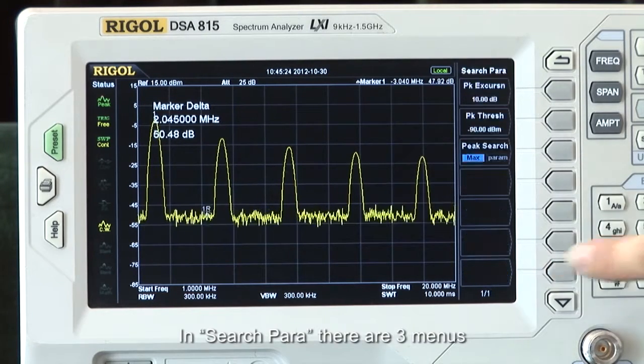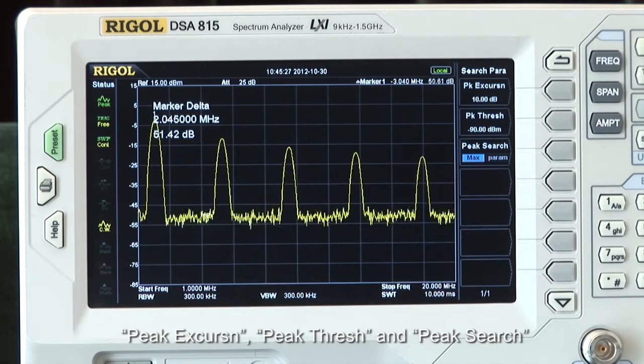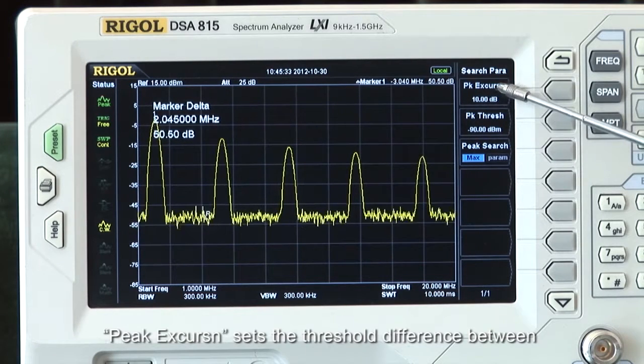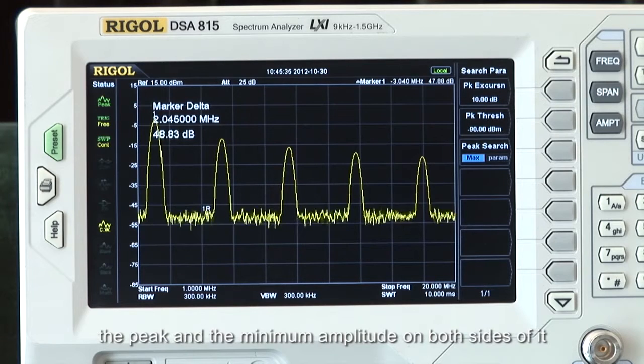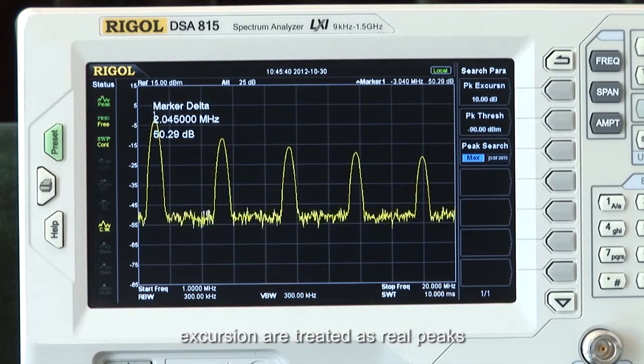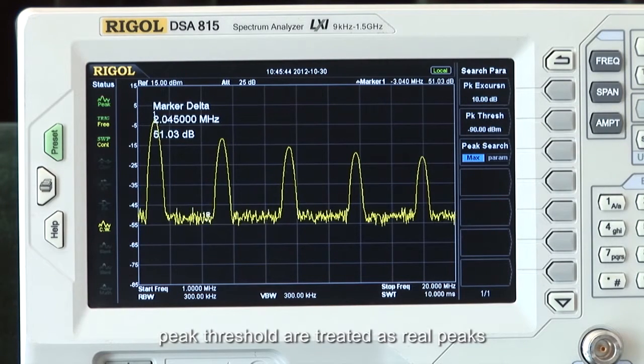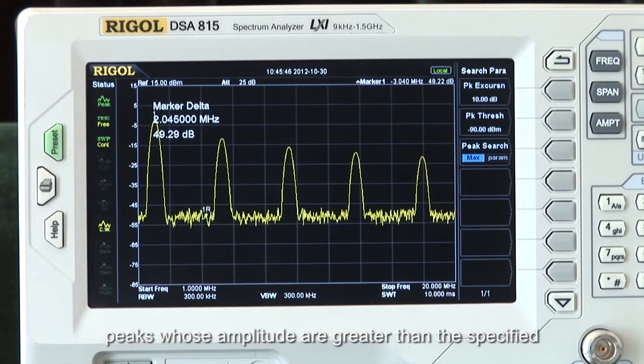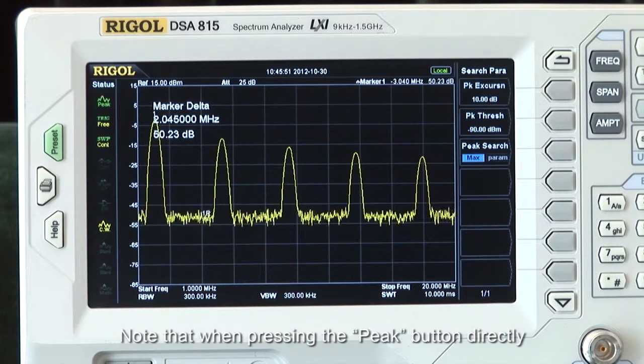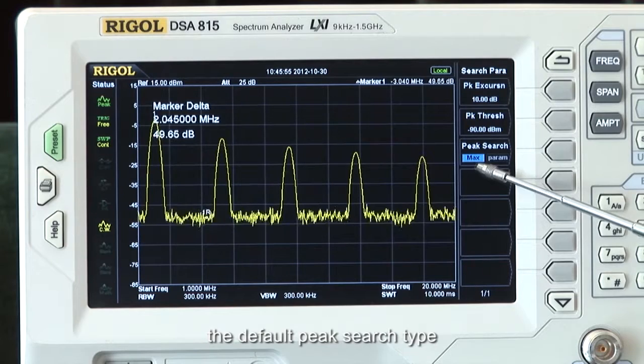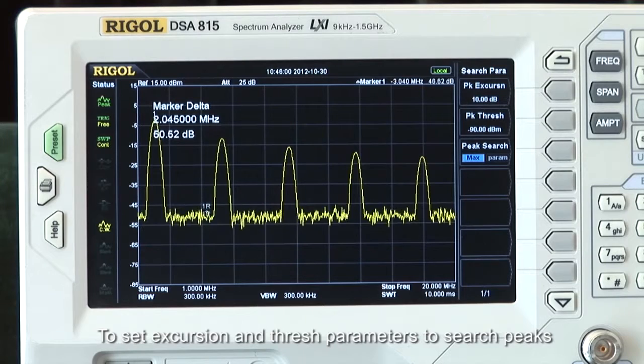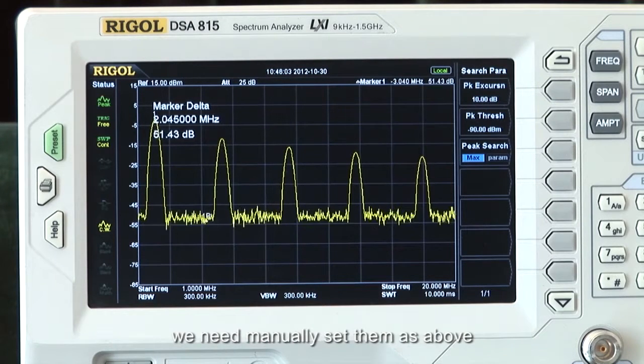In search parameters, there are three menus: peak excursion, peak threshold, and peak search. Peak excursion sets the threshold difference between the peak and the minimum amplitude on both sides of it; peaks whose excursions are beyond the specified difference are treated as real peaks. Peak threshold assigns a minimum value for the peak amplitude; peaks whose amplitudes are greater than the specified peak threshold are treated as real peaks. Note that when pressing the peak button directly, the default peak search type is set to look for the maximum amplitude of the trace. To set the excursion and threshold parameters to search peaks, we need to manually set them as above.